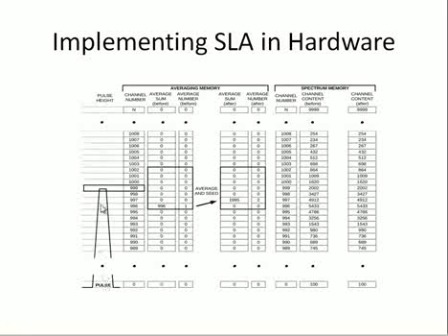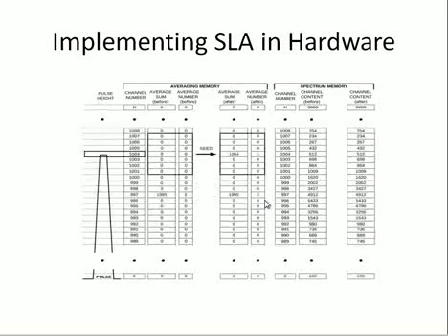Suppose now that we measure a second pulse height that comes in at 999. Now this pulse height does have an averaging window that's close to it. And so we're going to average 999 and 996, or sum them currently. So we're going to sum them and move the answer to the center where the average would be, and we increase the count by 1. So now there are 2 pulse heights in there.